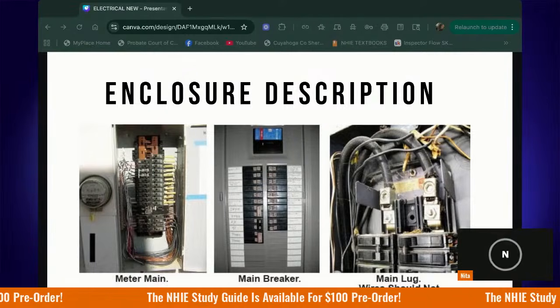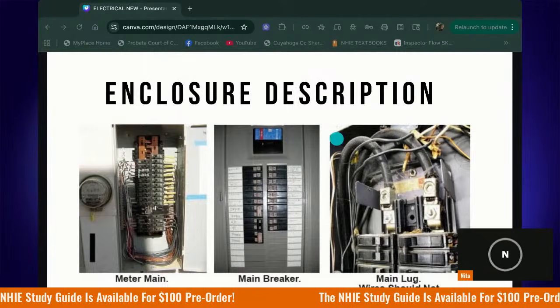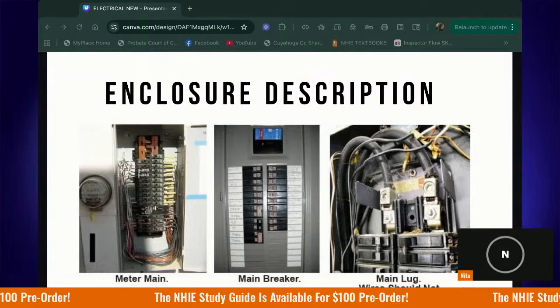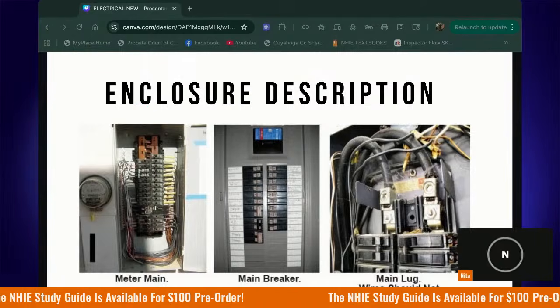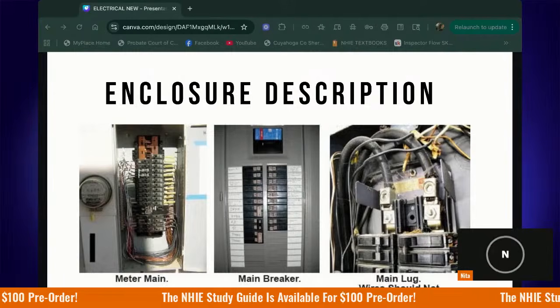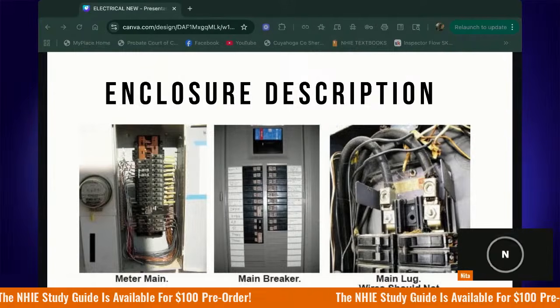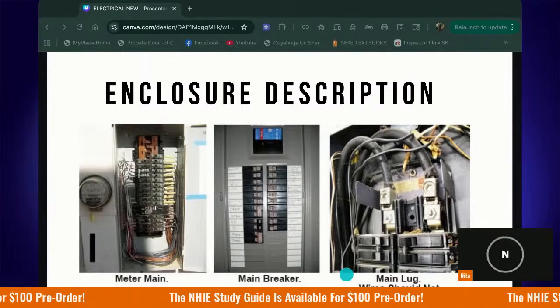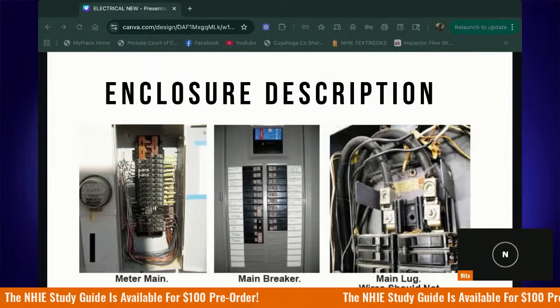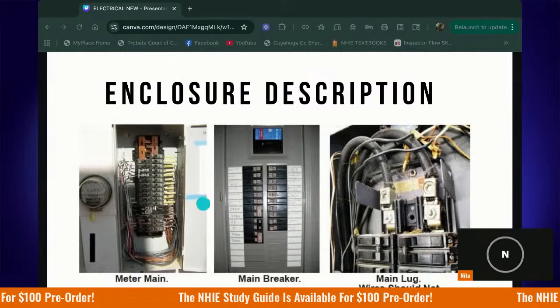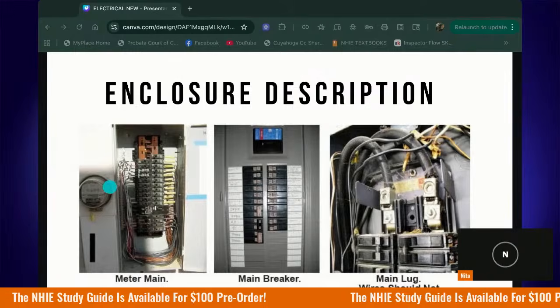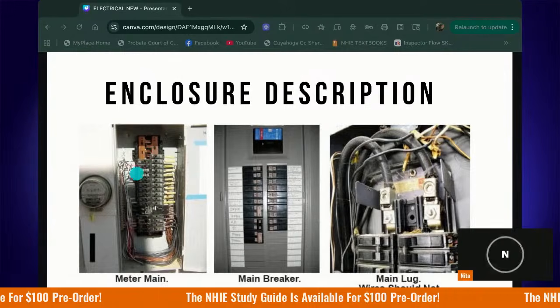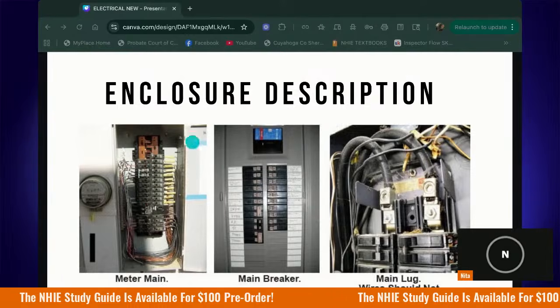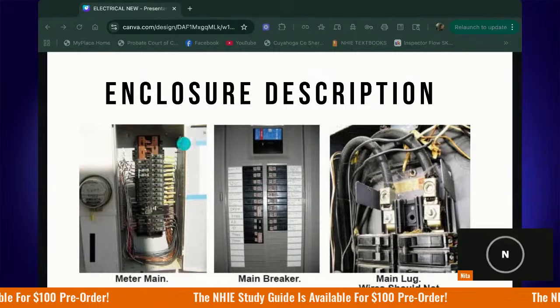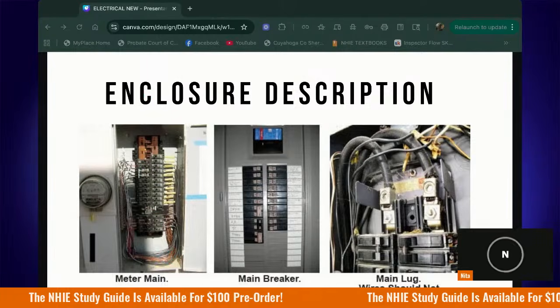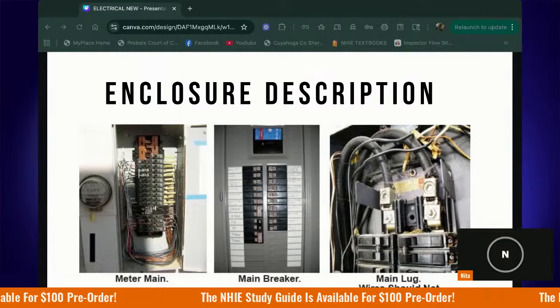And then we have three main enclosure types. So the meter main enclosure, okay, when we say enclosure, again, just think box. This is where you have the meter, the main disconnect, and a panel board in a single enclosure. Okay? So this is what you see here. You see the meter, the disconnect is somewhere on here, and the panel board for all of your branch circuits are located in one enclosure. This is a meter main. This is common in newer homes.